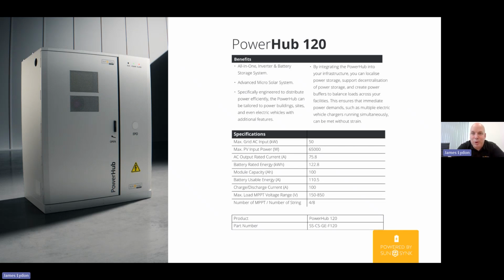These are pretty much plug and play units because the battery racks are all built with the batteries in. All the inverter connections are done inside. The only thing you need to do on site is terminate your final connections into it, whether grid or PV, and put the batteries into series. So really straightforward. And the Power Hub, the same as the rest of the range, we don't need PV connecting to our kit. So if you've got a customer who's got off-peak tariffs, or they just want to AC couple an existing grid side system, absolutely fine. No issues whatsoever.